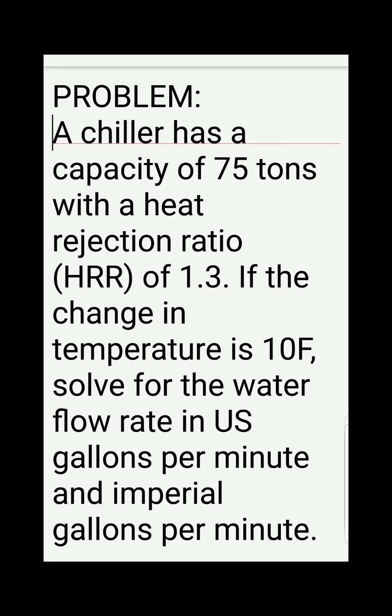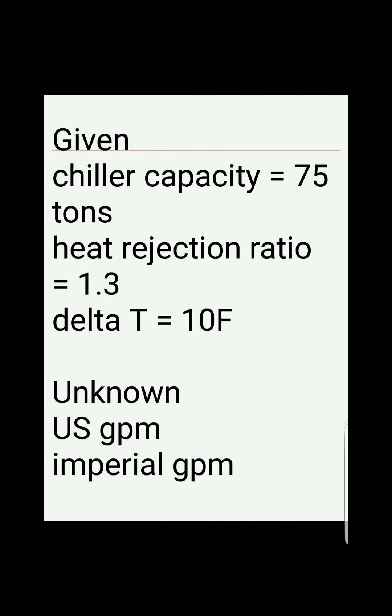We have a problem here: a water chiller has a capacity of 75 tons with a heat rejection ratio (HRR) of 1.3. If the change in temperature is 10°F, solve for the water flow rate in US gallons per minute and imperial gallons per minute. Given: chiller capacity of 75 tons, heat rejection ratio of 1.3, and Delta T of 10°F. Unknowns: US gallons per minute and imperial gallons per minute.